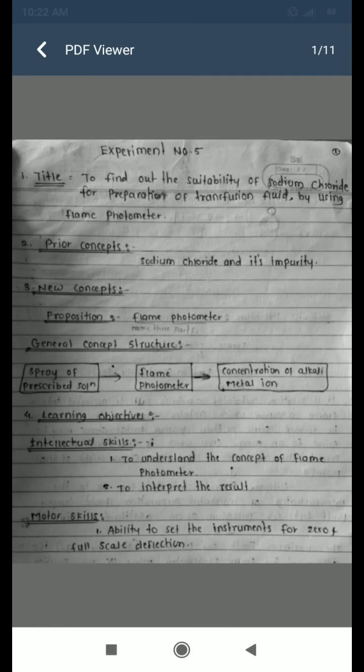There are four basic components to a flame photometer: a flame, a nebulizer and mixing chamber, color filters, and a photodetector. The learning objectives include the intellectual skill to understand the concept of the flame photometer and to interpret results, and the motor skill to set the instrument for zero and full-scale deflection and to note the correct reading.